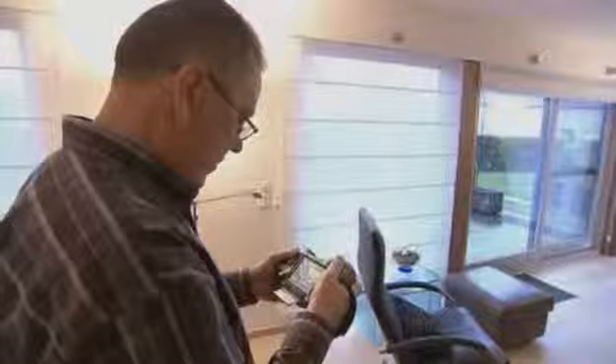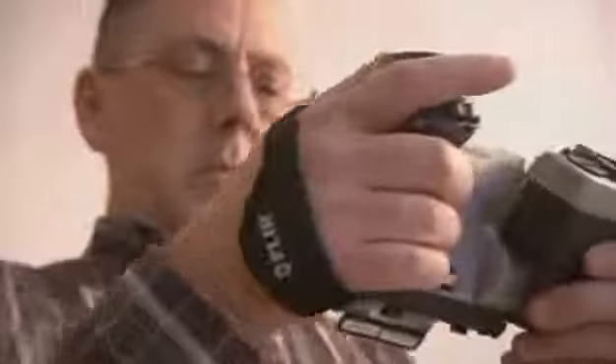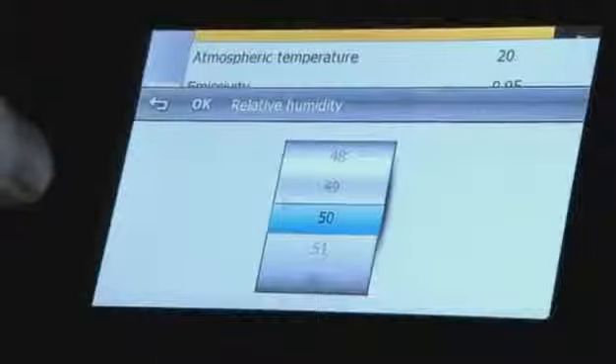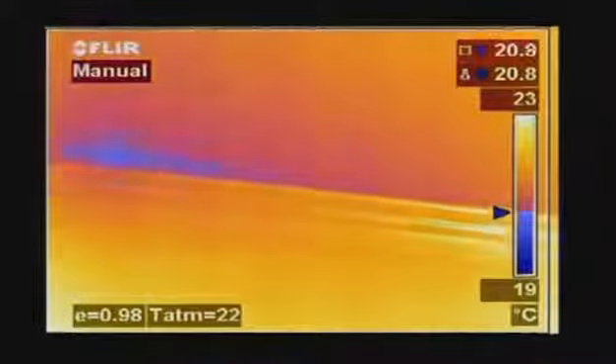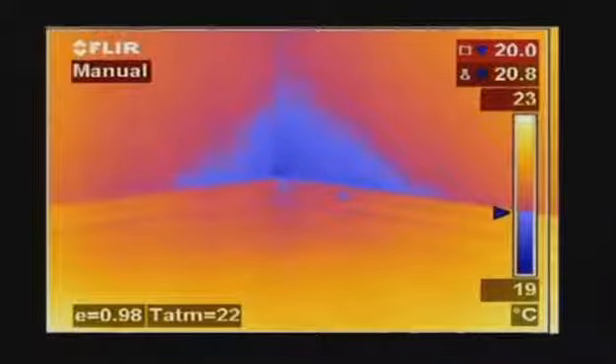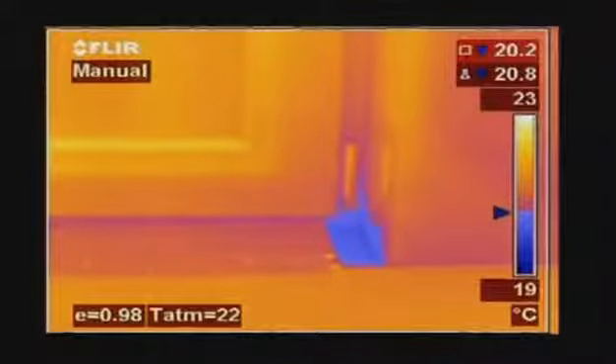If you don't have an Extech moisture meter to hand, all parameters used to identify potential condensation areas, such as relative humidity and temperature, can be set in the camera. The FLIR thermal imaging camera will calculate the dew point. Thermal imaging cameras with dew point visualization software can highlight endangered locations automatically and provide a color alarm in the image.